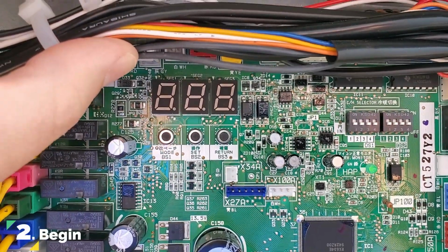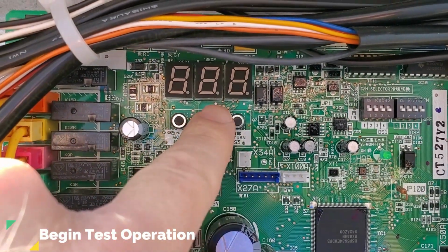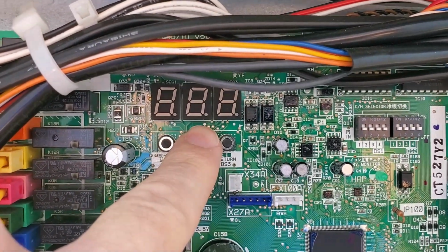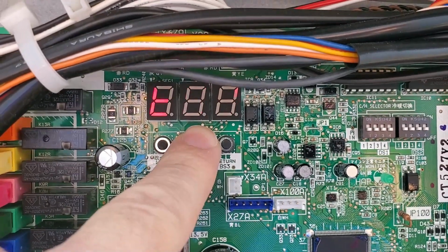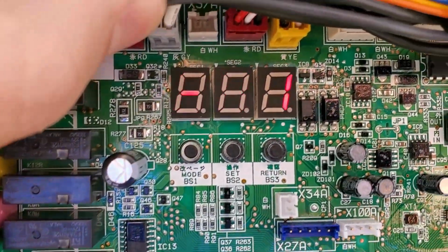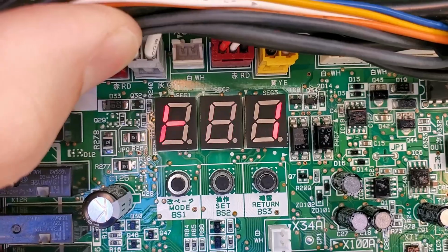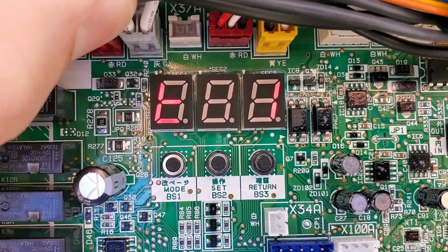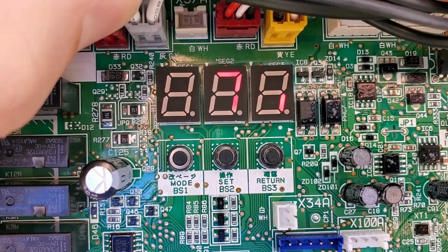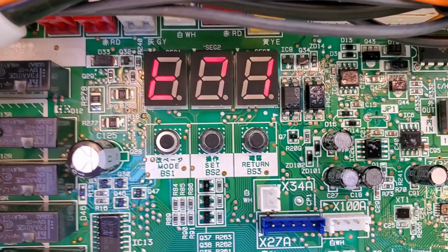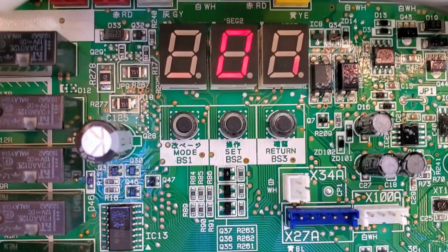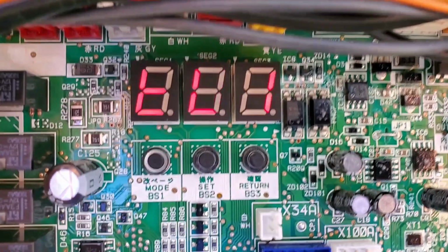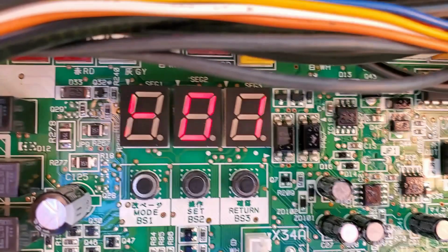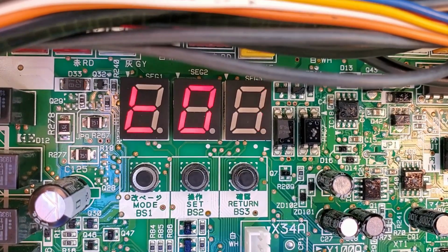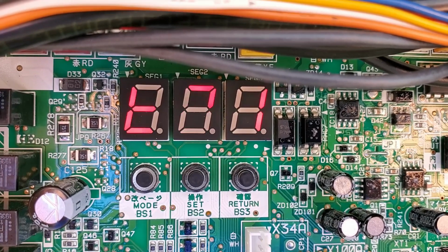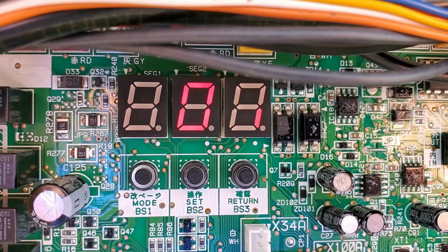All right, so once we're ready to run the test operation from a blank screen, all we need to do is press and hold the set button, and we're gonna press and hold it until the screen says T01. It'll be a little lowercase t with a 01. And you can, again, kind of see it on camera. You can see it in person really well though. It does say T01. It's also important to note that you do not want to start the test operation until you've added all of the remaining field refrigerant charge. We did not cover this in the last video because the contractor had already added all the field charge during the vacuum process. Test operation will take up to 1 hour, and during the test, the outdoor unit screen will change from T01 through T10. Once complete, the screen will go back to a blank screen automatically.